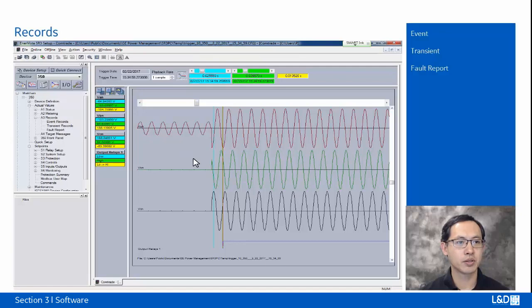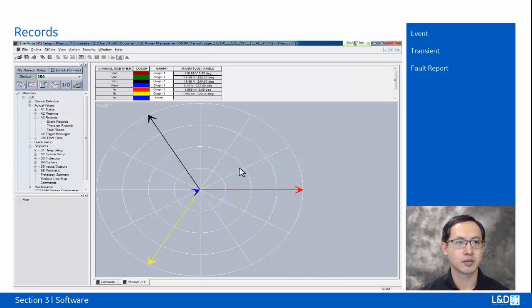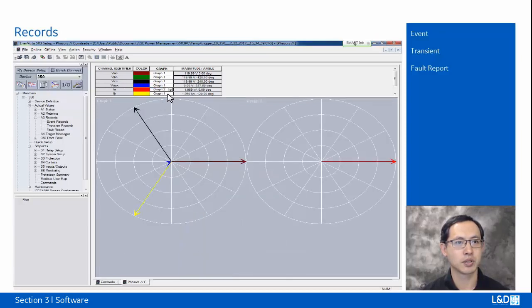And from this transient recorder, we can also see the phasor. By clicking the phasor, we can see the three-phase vectors and also the values, 120 volts, 0, 120, 240 degrees. And if you want to set the second group, you can choose current and voltage. So you can show two phasors. So that's lots of information included in this transient recorder. It's a very useful tool for troubleshooting.